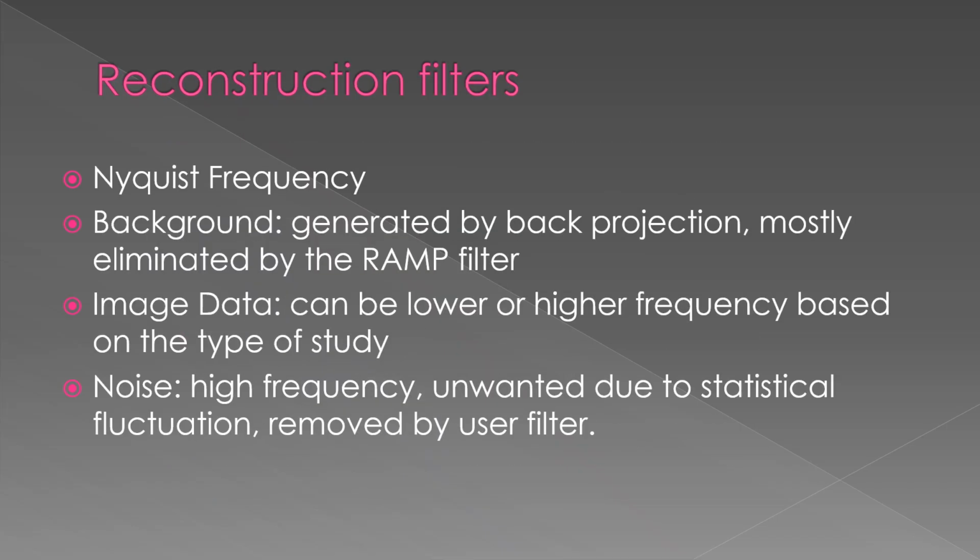Same kind of reconstruction technique applies to PET that applies to SPECT. The Nyquist frequency is really important. Remember, that's the highest frequency that it can do, kind of the limitations of the system. And the background is generated by back projection, mostly eliminated by a ramp filter. And then the image data can be lower or higher frequency based on the type of study. Noise is always high frequency, and this is unwanted.